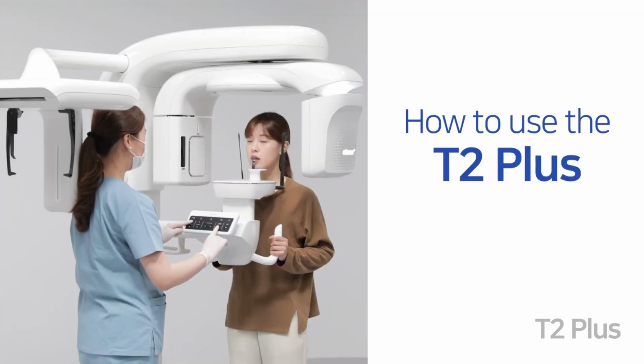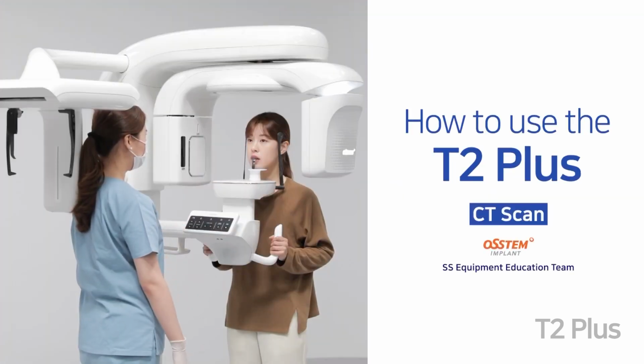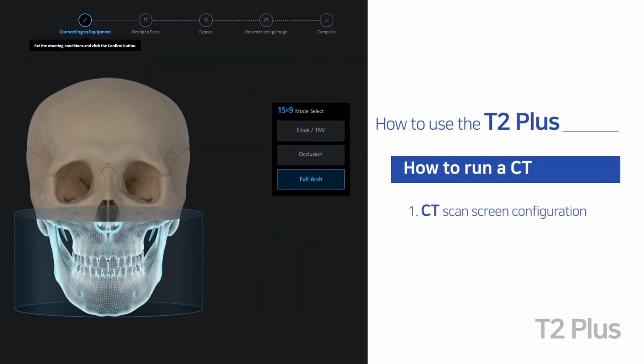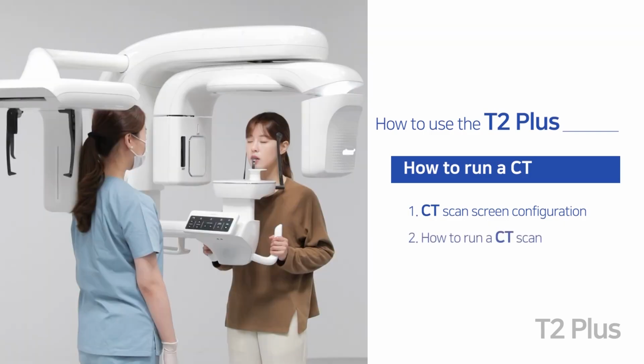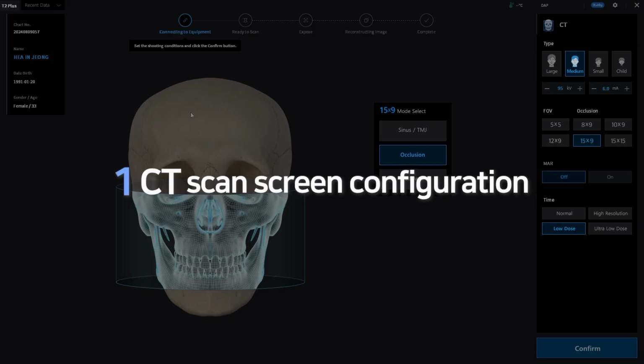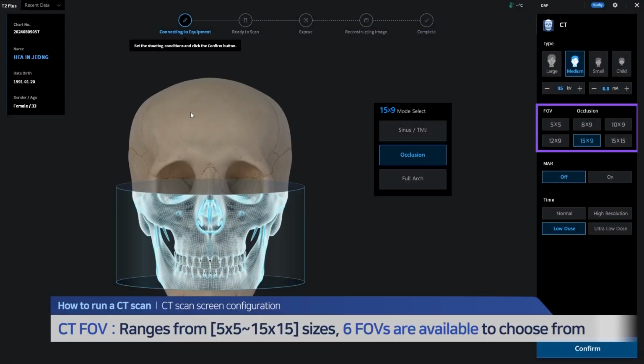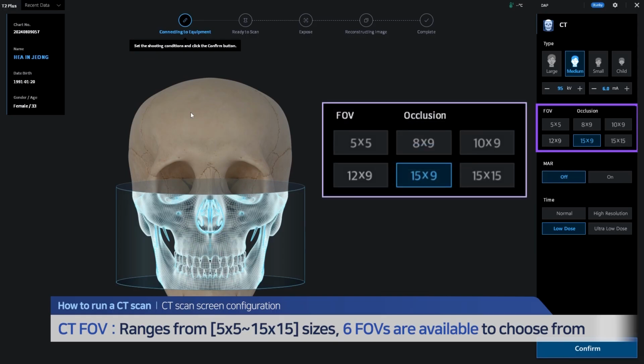Let me walk you through how to run a CT scan using the T2 Plus. First, we'll be talking about the CT scan screen configuration, then how to run a CT scan. First, let's look at the CT scan screen configuration. There are 6 different CT FOVs ranging from 5x5 to 15x15 to choose from.